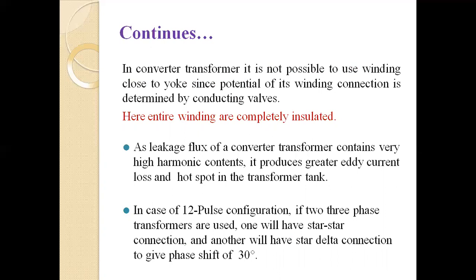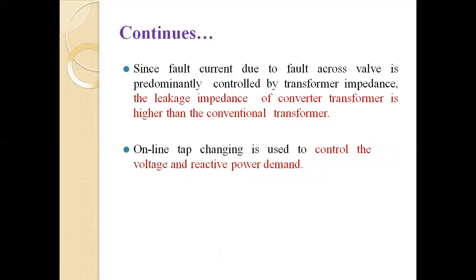In case of 12-pulse configuration, if two three-phase transformers are used, one will have star-star connection and the other will have star-delta connection to give a phase shift of 30 degrees. Since the fault current due to a fault across the valve is predominantly controlled by the transformer impedance, the leakage impedance of the converter transformer is higher than the conventional transformer.